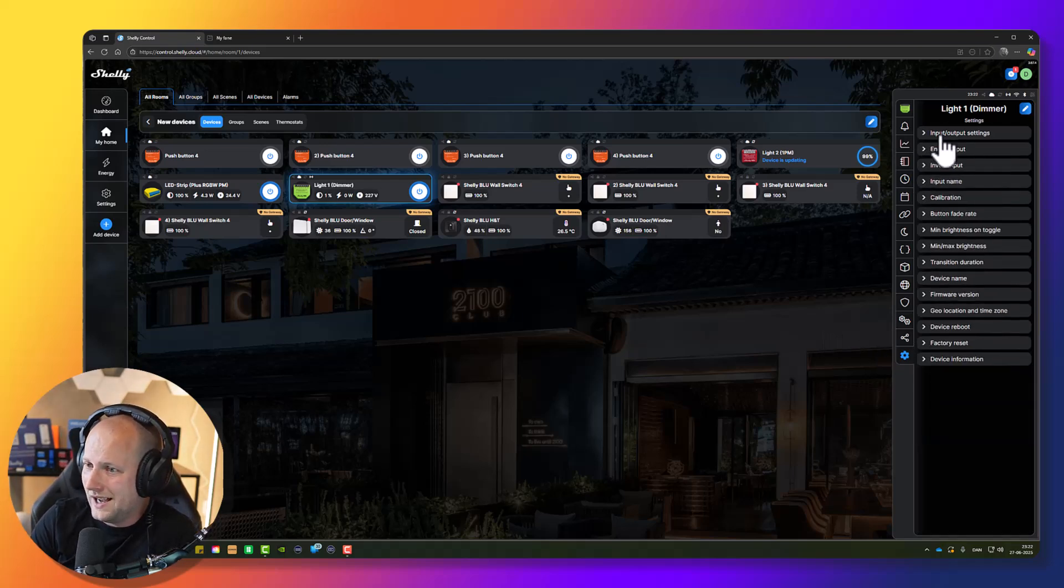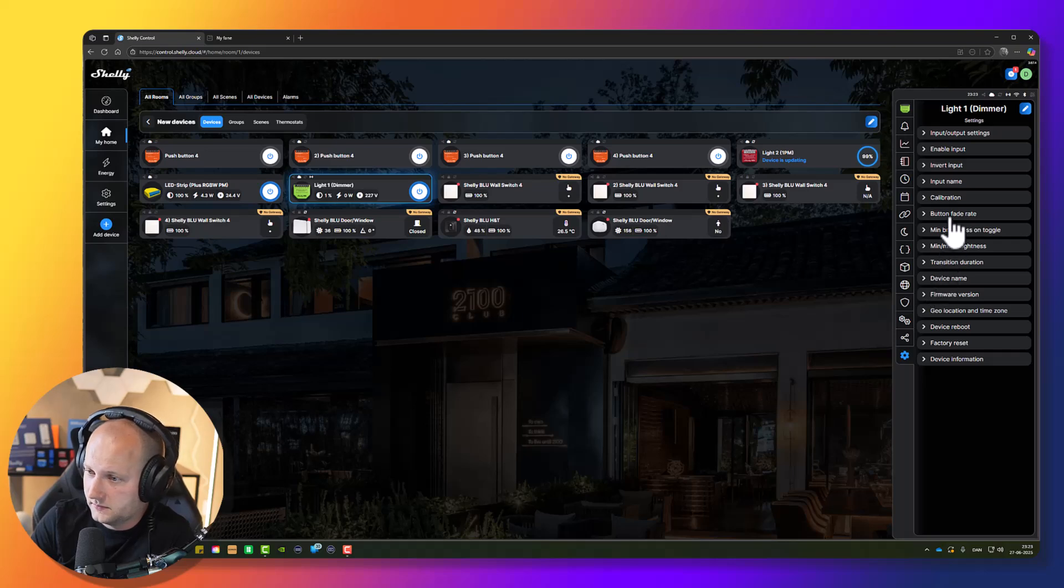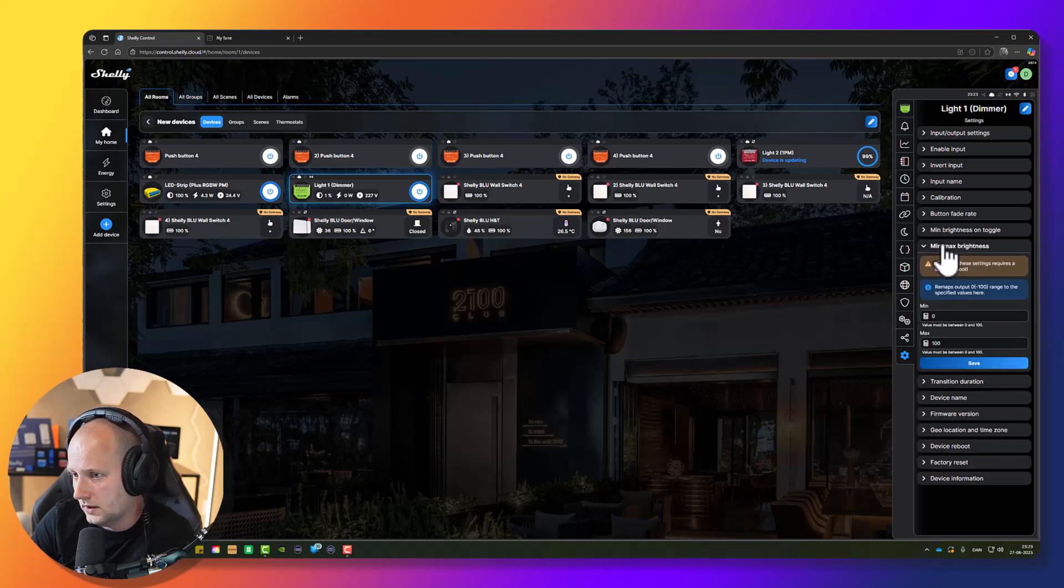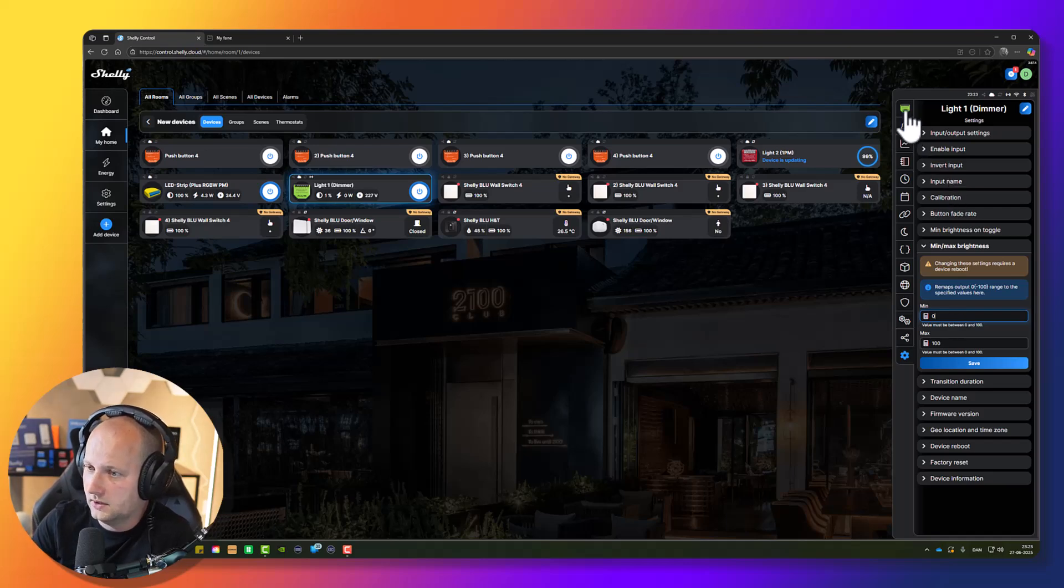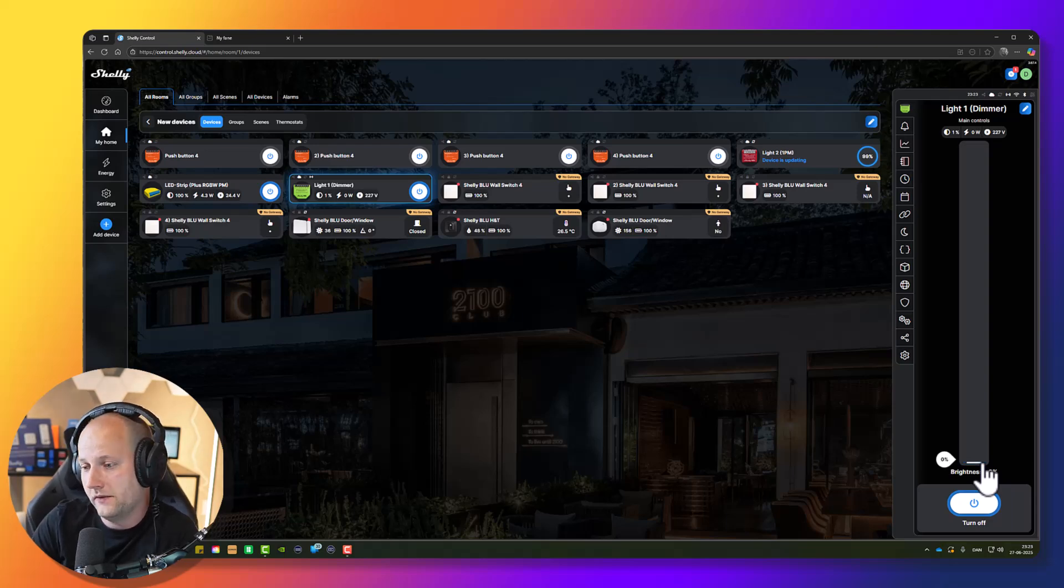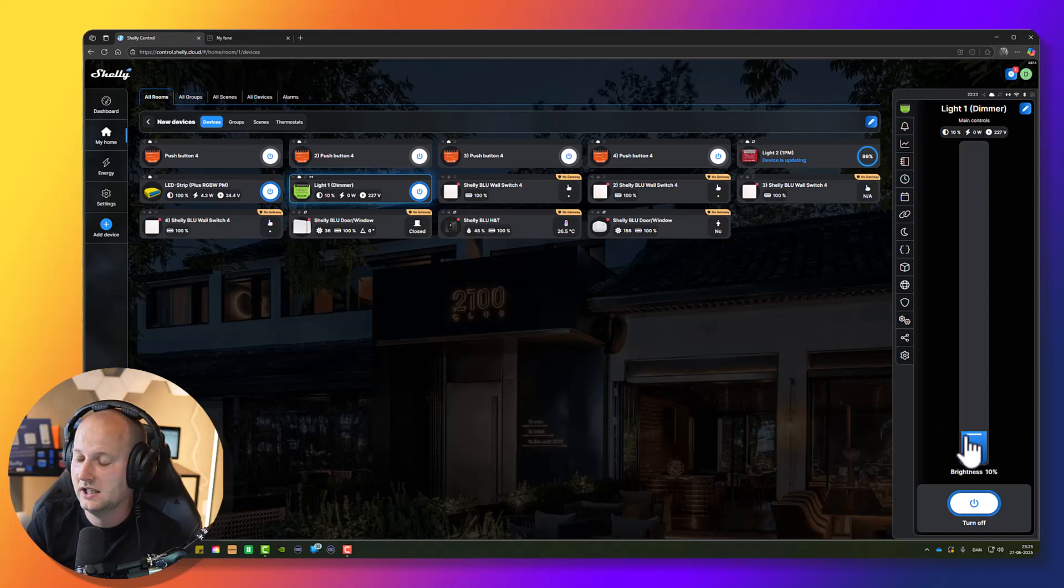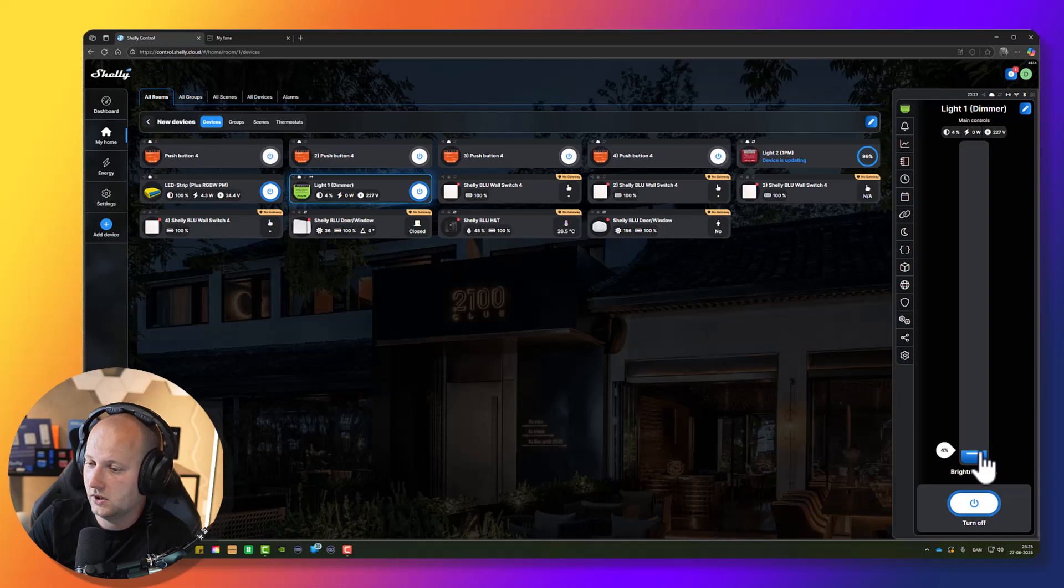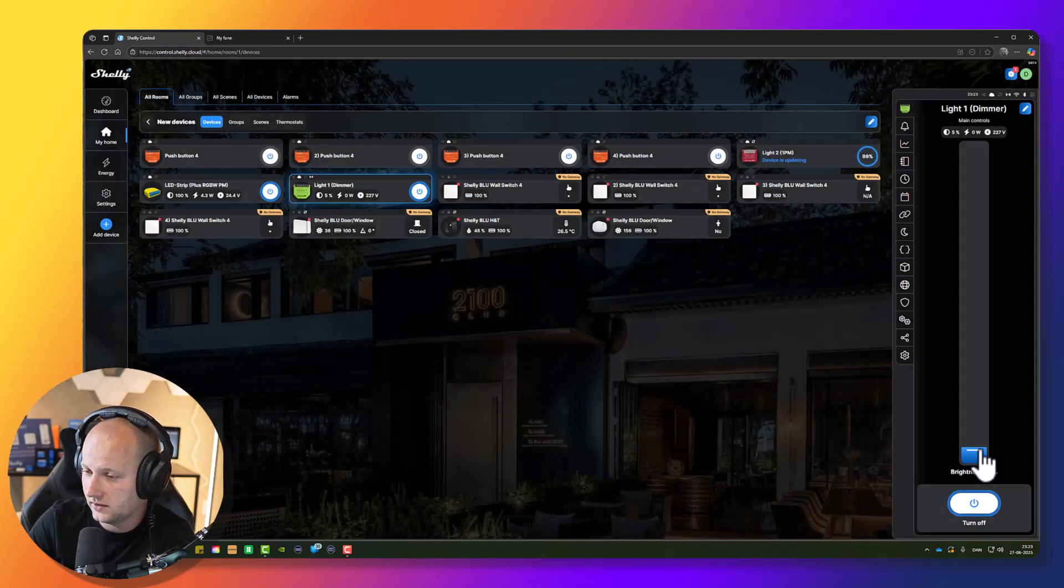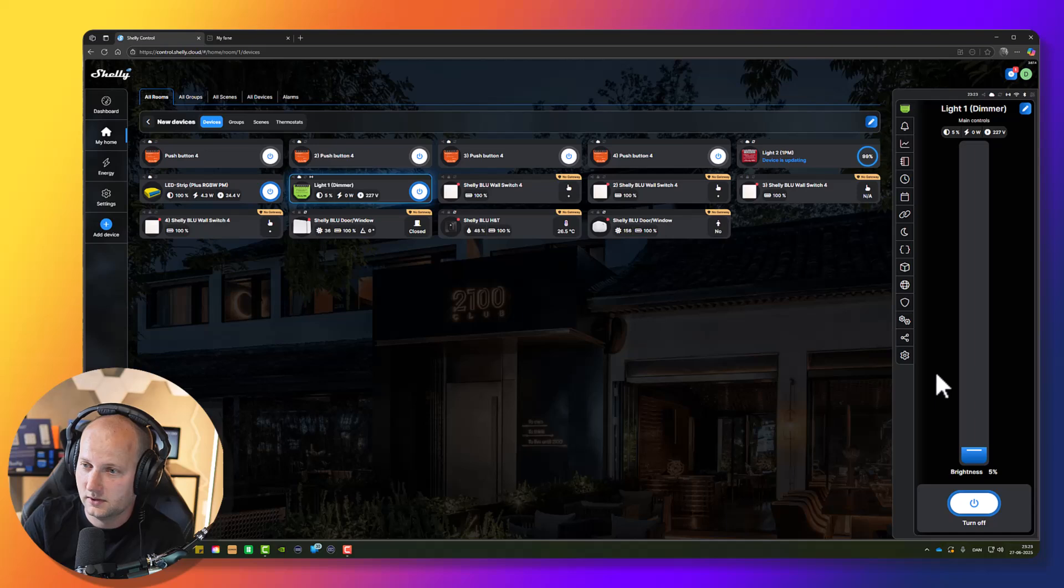I would like to check the dimming level though. Next thing is to change the minimum brightness level. Minimum brightness level is zero. Let me see, when I dim all the way down it does not turn off. It stops on one percent. This is very good. Very often when you have LED bulbs, you need to set the minimum brightness level to five or sometimes ten percent depending on the quality of your LED bulb. If you have an LED bulb which turns off when you dim down to four percent, I would prefer to set the minimum brightness to five percent to make sure the customer will never dim down too much so the device turns off.